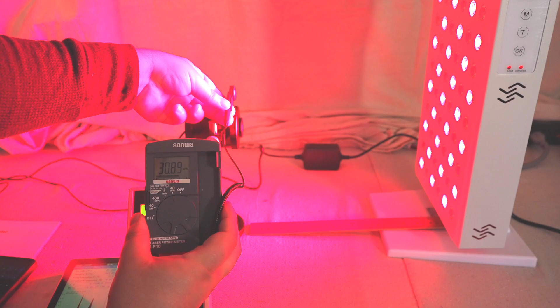And like I said, the Sanwa is kind of a pain in the butt because now we have to take our measurements from this calibration curve. So we have to do a weighted average of these numbers, and then we have to divide by the sensor area. I think some people think I'm trying to bamboozle them with made up numbers, but it's just because they don't understand basic math and linear interpolations. And then, like I said, dividing by the sensor area. It's pretty straightforward. So we're going to take 31, and then we multiply by 0.83. That's the calibration factor for the wavelengths. And then we divide by 0.636, and that gets us 40.